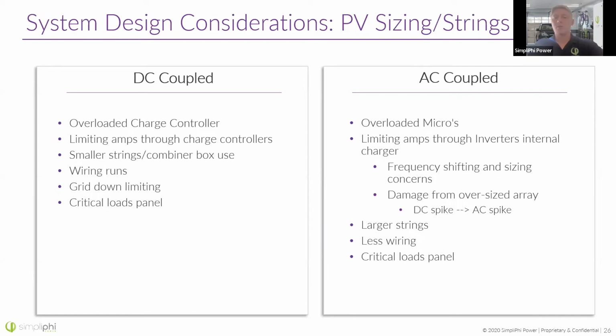And then also just knowing that limiting amperage through an inverter's internal charger is not as reliable as limiting it through a charge controller. Some inverters don't even have the ability to limit that charge current and the power output of the inverter. Most of them do, I would say. All of the new inverters coming out have these settings, but some of the older ones do not.